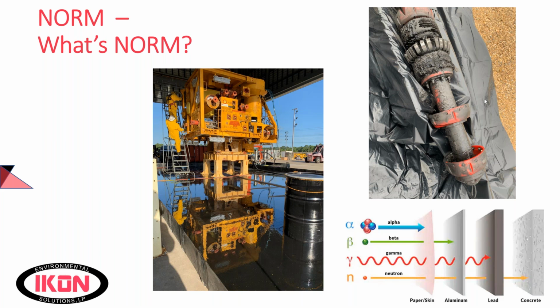When you're looking at surface contamination, alpha and beta, typically people have a pancake detector. It's the trade name for it. It's a Geiger-Müller counter, gas filled detector, and you get counts on that. So you have to take into account detector efficiency and detector geometry, how big your detector face is, because regulatory limits are expressed in units of 100 square centimeters, and our detectors aren't 100 square centimeters. So there are some conversions you have to do.